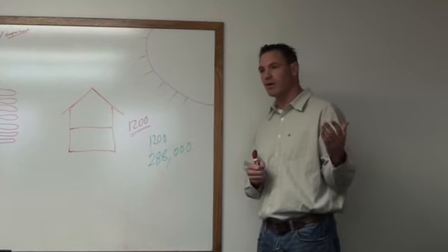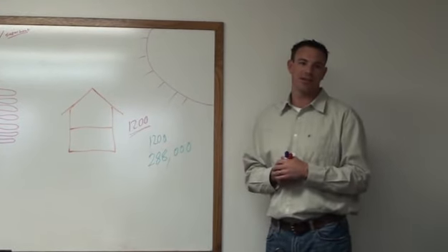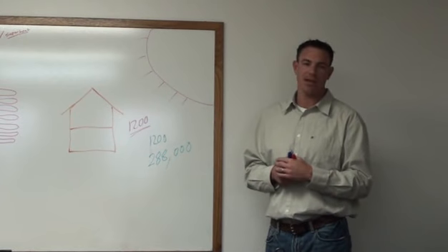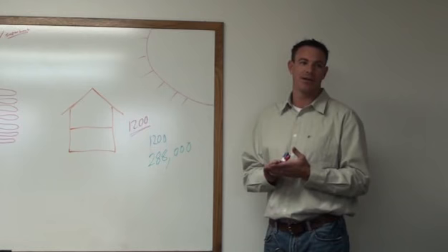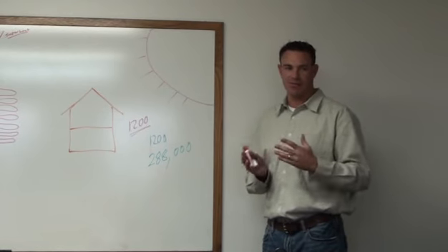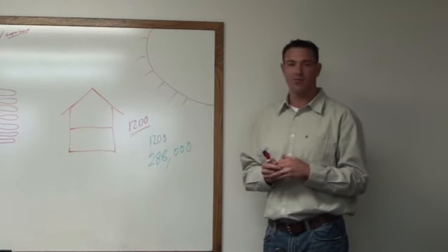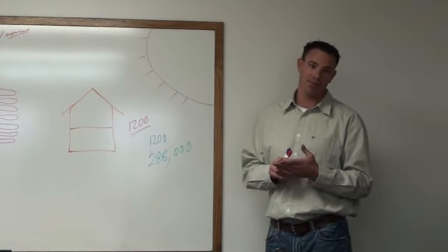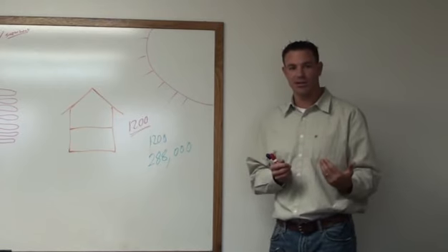care of the whole 1,200 square feet, if you do the calculations that I've just given you, it's not going to do the job. It's just going to run and run and run, cost a lot of energy, and eventually have some sort of mechanical failure, and eventually give out and probably not work, and you're going to get a complaint.